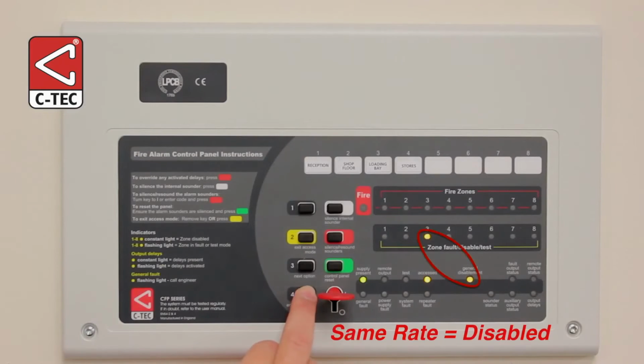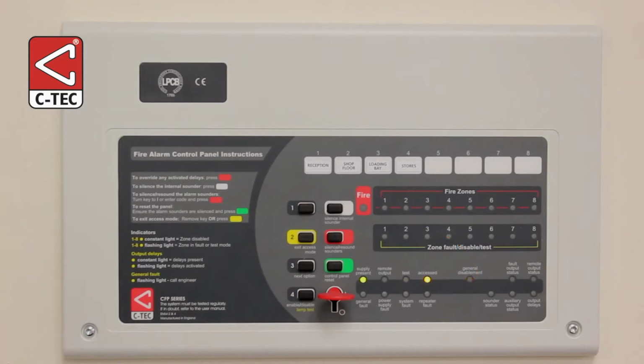Press the Enable Disable button to toggle between enabled and disabled. As we want to disable Zone 3, we need to make sure the two lights are flashing at the same rate. To confirm the selection, press the Next Option button. This moves the selection process onto the next available option, in our case, Zone 4.